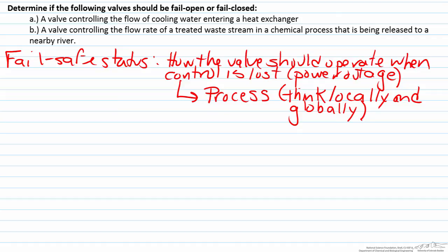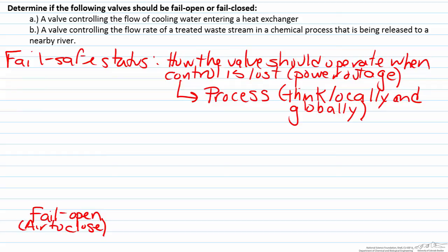There are two types of fail safe statuses for valves. The first is fail open, also known as air to close. Many valves are pneumatic and based on air pressure, so we need to increase the air in order to close the valve, because that is the opposite of the fail safe status. If the valve fails with no air, we want the system to be fully open, so more air is required to close it.